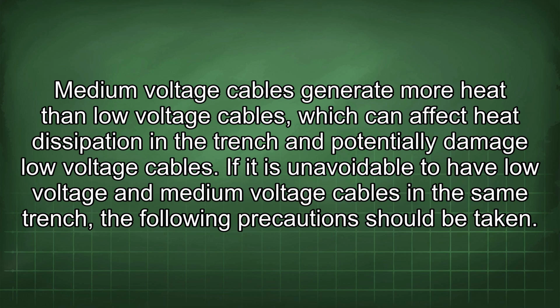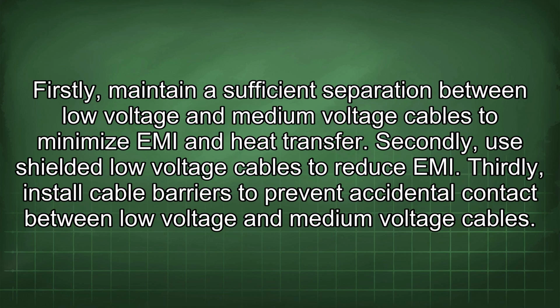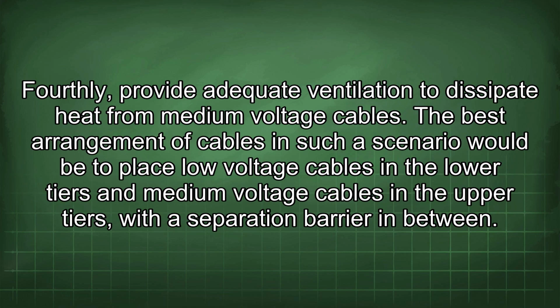If it is unavoidable to have low voltage and medium voltage cables in the same trench, the following precautions should be taken. Firstly, maintain a sufficient separation between low voltage and medium voltage cables to minimize EMI and heat transfer. Secondly, use shielded low voltage cables to reduce EMI. Thirdly, install cable barriers to prevent accidental contact between low voltage and medium voltage cables. Fourthly, provide adequate ventilation to dissipate heat from medium voltage cables.